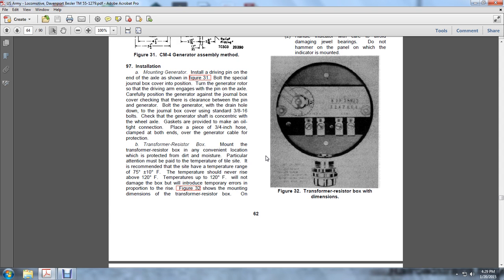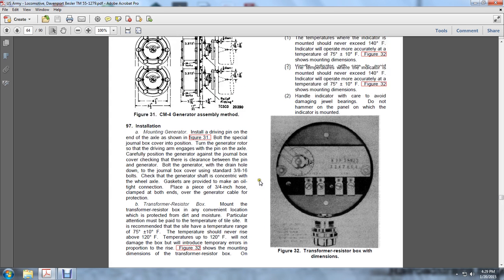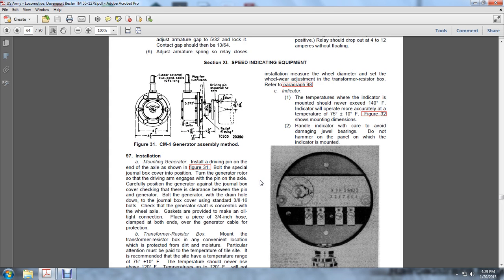Temperatures above 120 degrees Fahrenheit will not damage the box, but will introduce temporary errors in proportion to the rise. Showing the mounting dimensions of the transformer resistor box on the installation. Measure the wheel diameter set for the wheel adjustment of the transformer resistor box. Refer to paragraph 98. The temperature at the indicator mounting should never exceed 140 degrees Fahrenheit. Indicators are more accurate at a temperature of 75 degrees plus or minus 10 degrees Fahrenheit, as shown in the mounting dimensions.